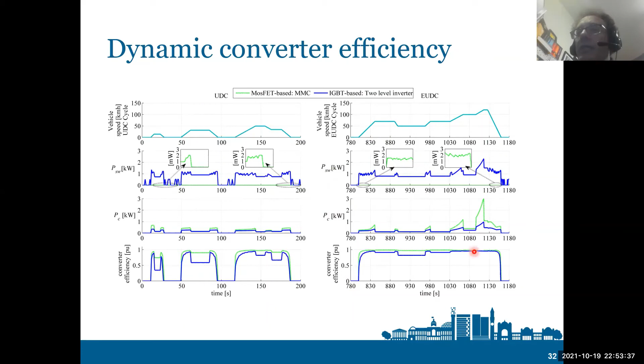In this slide we have compared the static converter efficiency, and as you can see, for the modular converter, shown as the green line, it is actually slightly smaller than the efficiency of a traction inverter operated with a switching frequency of 2 kilohertz, but it would be slightly better than a traditional converter operated with a switching frequency of 20 kilohertz. When we look at full load current, they are almost comparable.